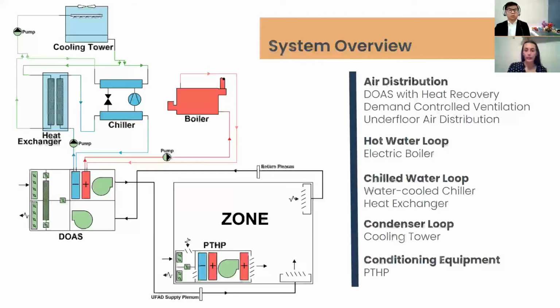Now, taking a look at the system overview, we see that the ventilation is served by a direct outdoor air system, which will provide 100% conditioned air to the zone. The DOAS is paired with a heat recovery in order to recover heat from the return air. We can achieve a higher heat recovery efficiency by using DOAS rather than a common in-suite heat recovery method, since the equipment is larger and has more free space for a larger heat recovery. The DOAS is also paired with a demand-controlled ventilation device using CO2 sensors in order to reduce the ventilation when needed. The DOAS is served by an electric boiler and a water-cooled chiller in order to condition the outdoor air.